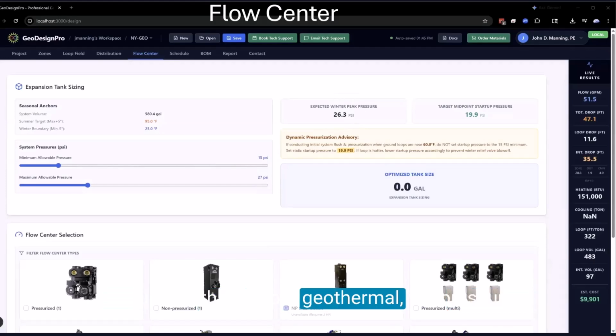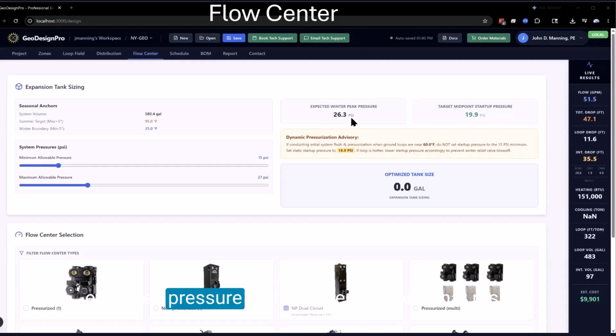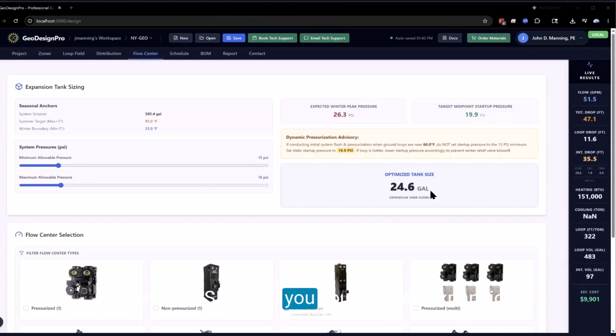The unique thing about geothermal, the pressure change in the system is counterintuitive. The pressure actually goes up as the loop gets colder. So we display that up here, that if you set your minimum at 15, we're assuming that's going to be in the summertime. And then it calculates the expected pressure in the wintertime. And that results in roughly a 12 psi swing from winter to summer. But if you wanted to tighten that up, say you wanted it only 1 psi, it'll tell you you need an expansion tank capable of handling 24.6 gallons of fluid.